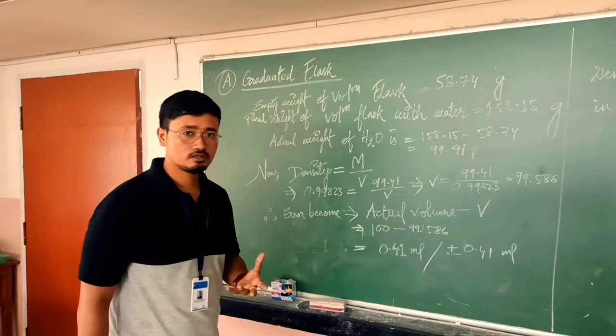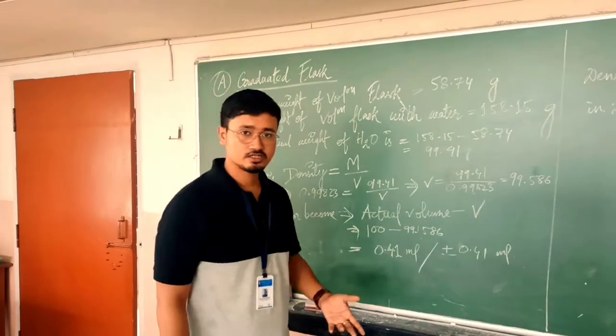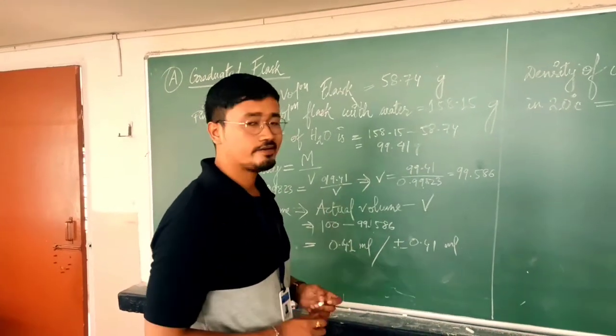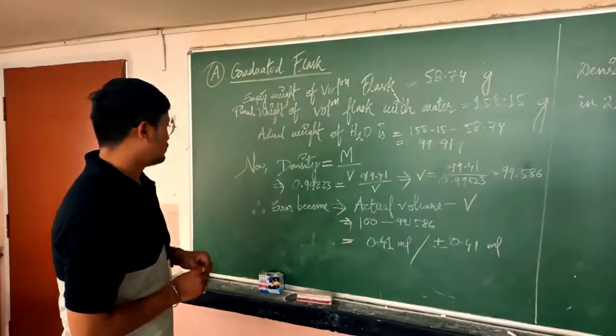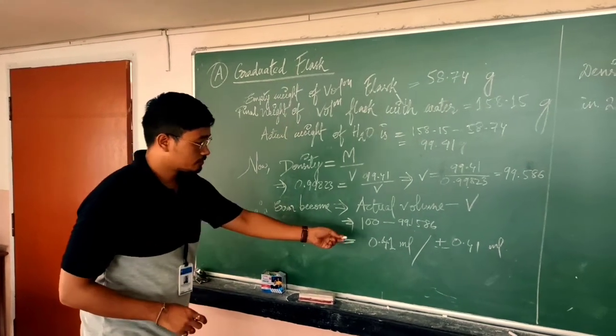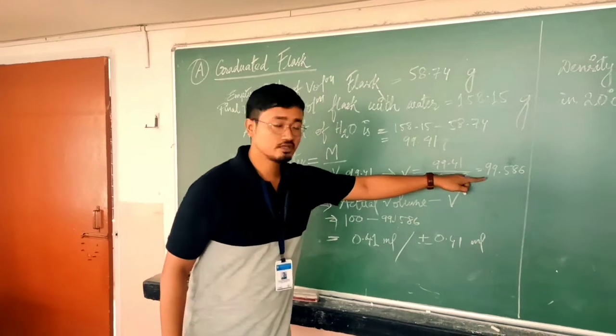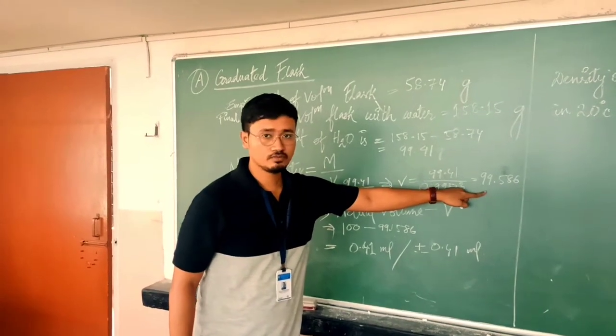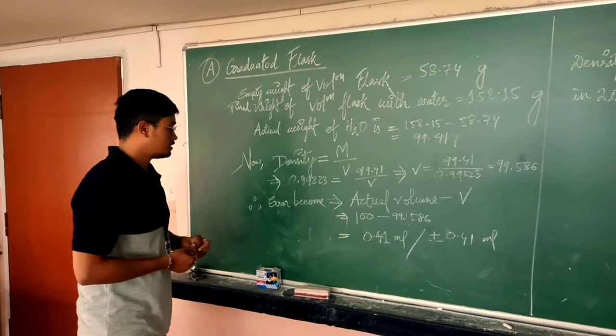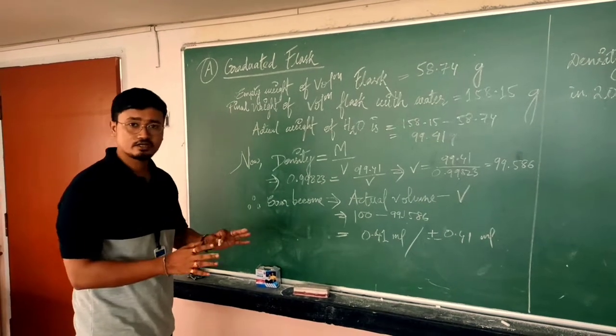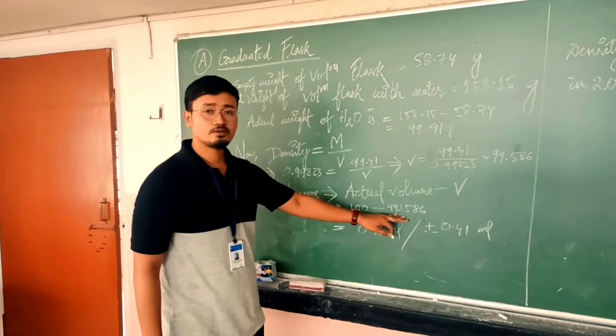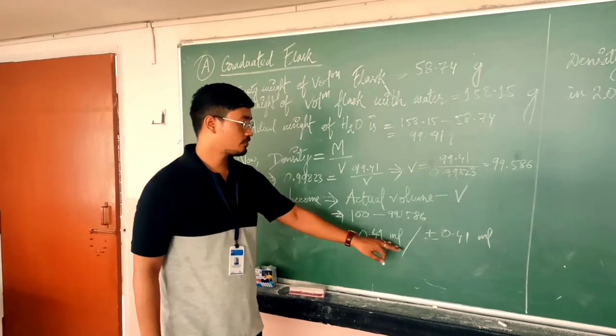The temperature of water at the time of the experiment was 20 degrees Celsius. At that particular temperature the density of water is 0.99823. By putting that value in the formula, we will get the volume, which is 99.586. This is the actual volume of the volumetric flask. The volume written on the volumetric flask was 100 ml, but the actual volume we got is 99.586 ml, so the difference is 0.41 ml.